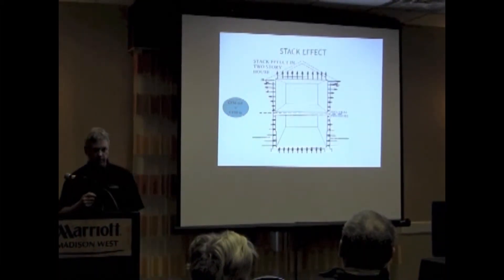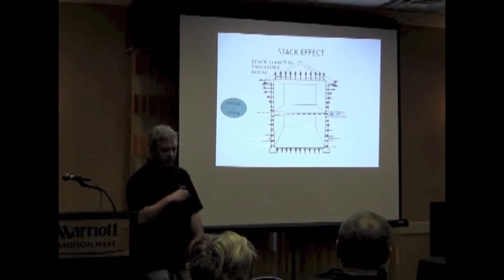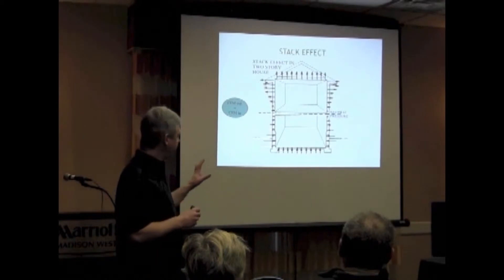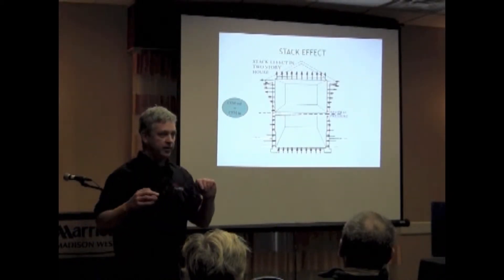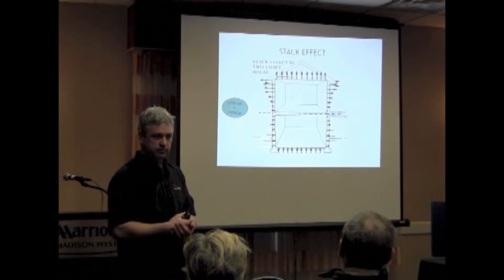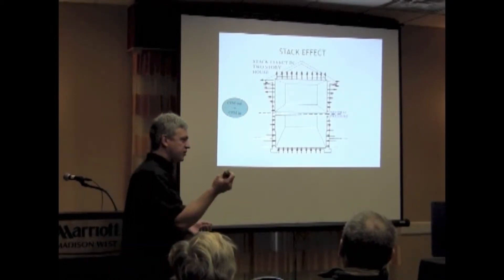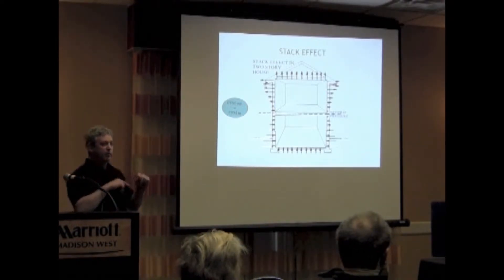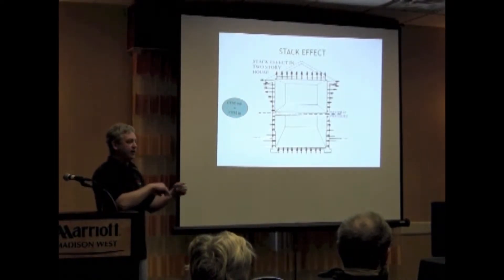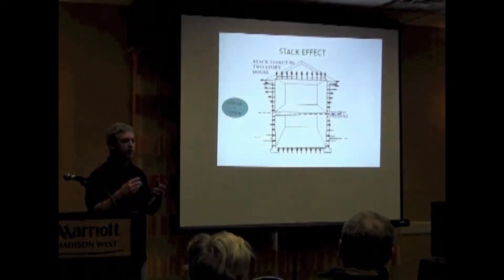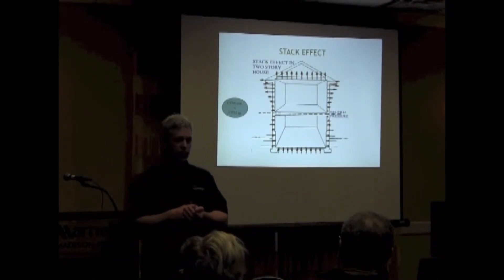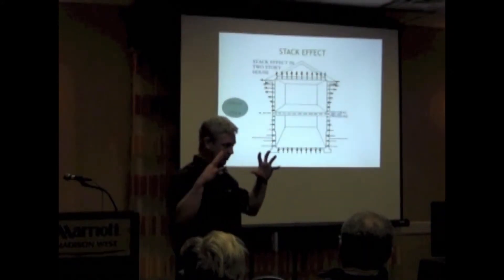This is the stack effect. If you have air going out of your home, you'll have air coming in. The cubic feet per minute — if you can imagine a basketball, that's a cubic foot. So if I come and test your house, I'm going to put my blower door in the house and it's going to tell me how leaky your home is in cubic feet per minute. It might give a number like 1,500 — meaning 1,500 basketballs can move through your home if I put a 15-mile-an-hour breeze on the outside of the house.